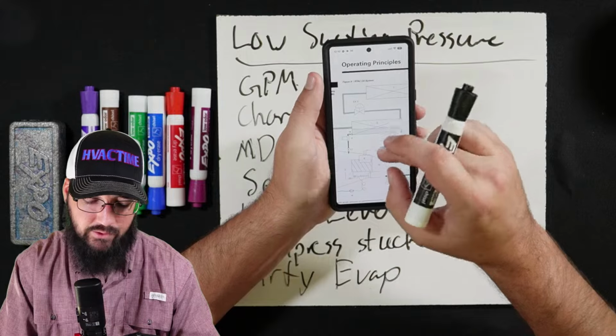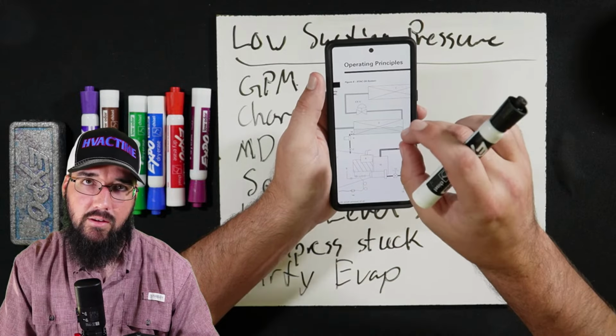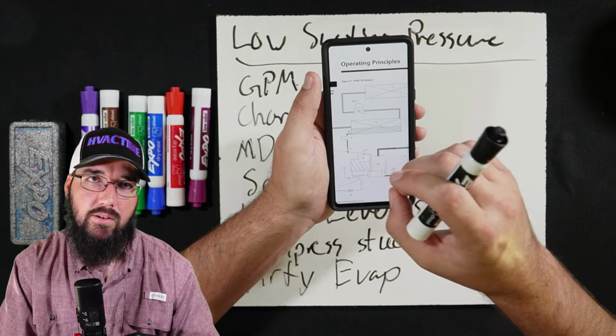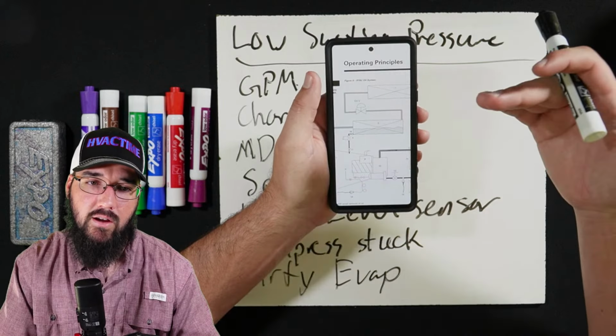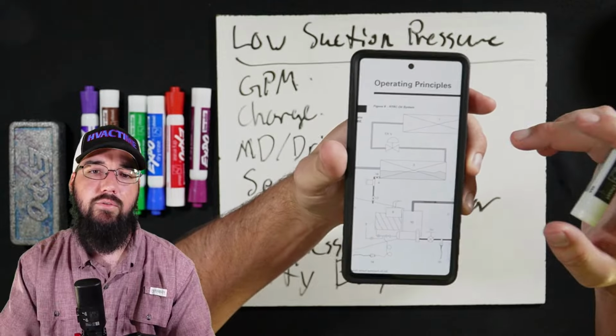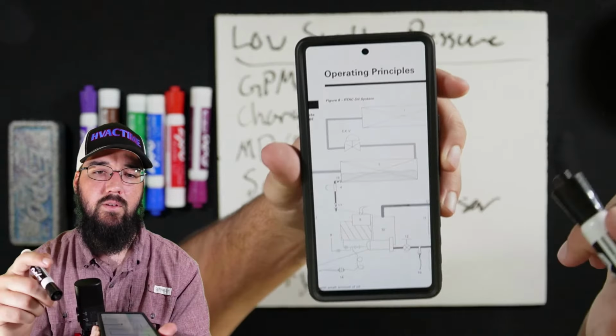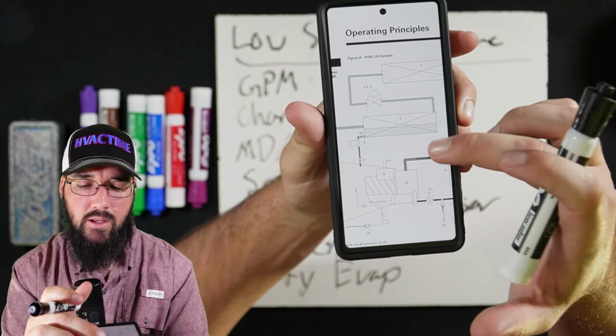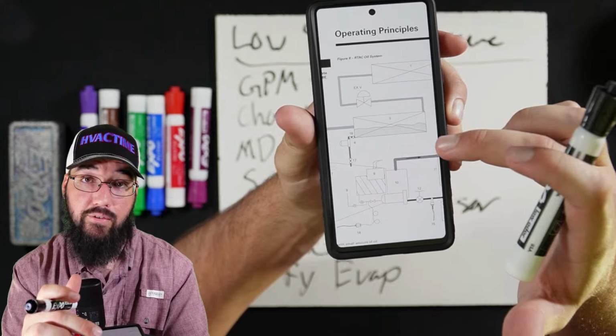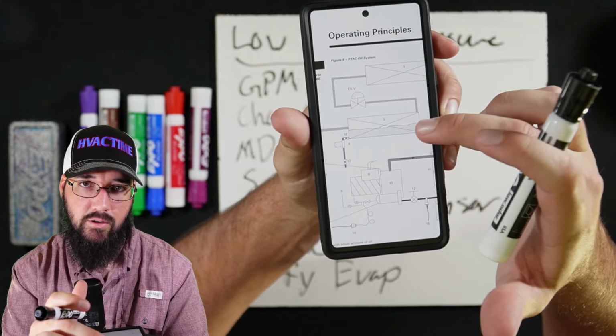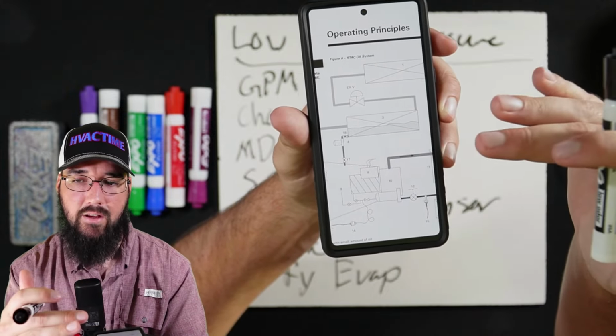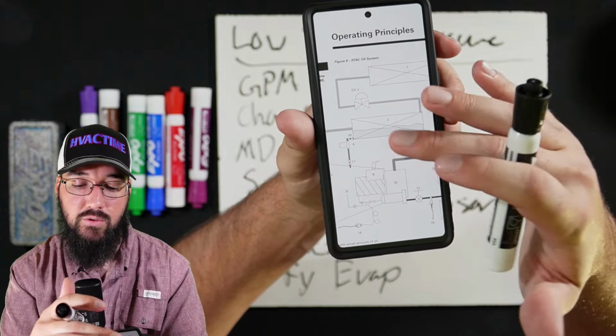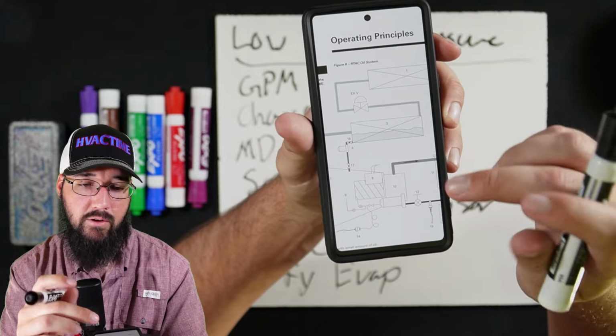These do not feed into the bottom. Because the two-phase line and the metering device feed into the top, that's an immediate giveaway of a falling film style, which means they run a much lower liquid level. They don't stack a lot of refrigerant in the bottom. It's going to be very minimal.